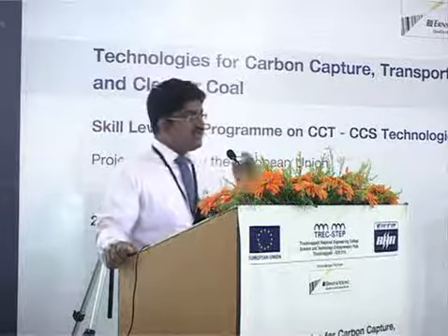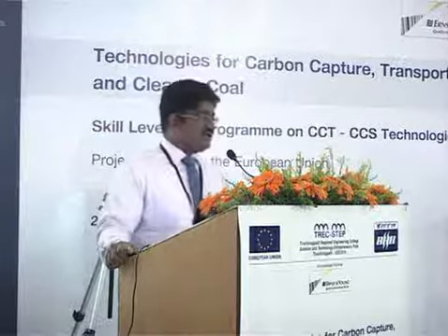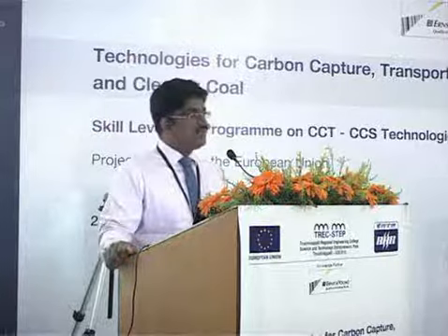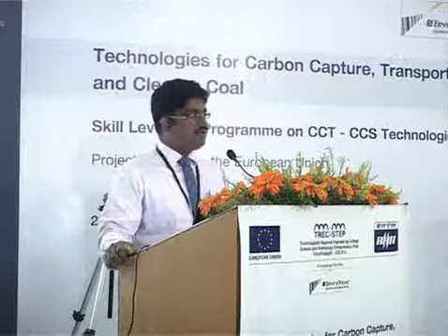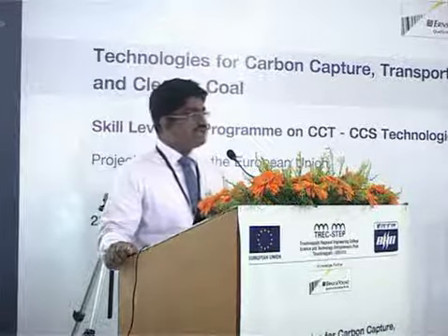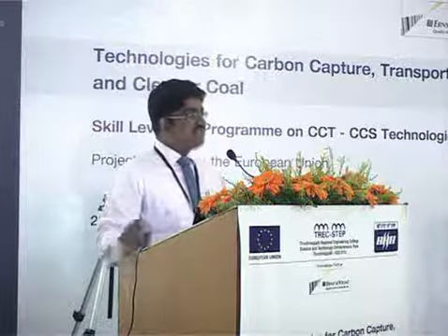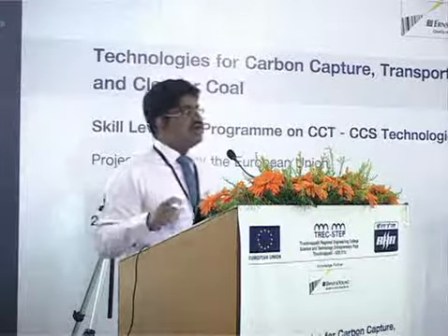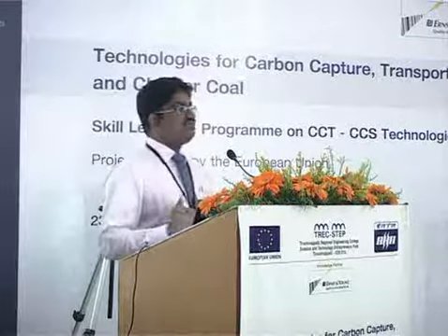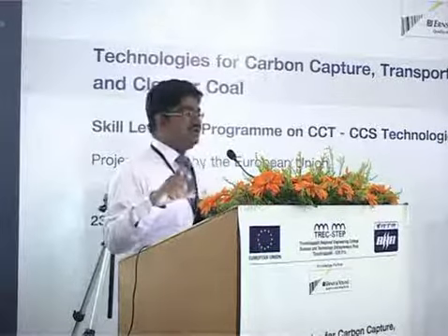Find out what your accelerated depreciation is, with respect to your Companies Act and your Income Tax Act, subtract it, find out your loan component, take it out, then what your annual operating expenses are, and what your revenue is. Revenue minus expenses, it's something like a cash flow analysis that you have to do. The net cash output you have to divide by the total kilowatt hours, that is the number of units you are going to generate.